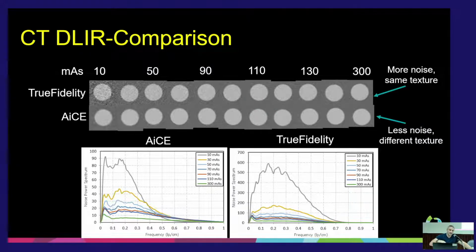So I did this analysis right here. I went through this exercise. I wouldn't go in and turn my scanners down to 90 mAs, but I know that there's a certain point, roughly about the 60-70% point, where I'm going to start losing texture. So if I were to go into the clinic and do a dose reduction, I would feel very comfortable reducing probably around the 50% level, just turning it there without concern. After that, I'd probably start inching it down and using radiologists to make sure I got it right. So phantoms are good to get you in the ballpark, and you can use the phantoms all different ways.